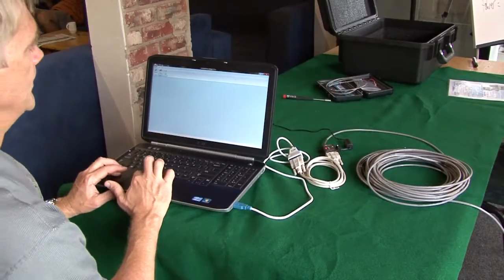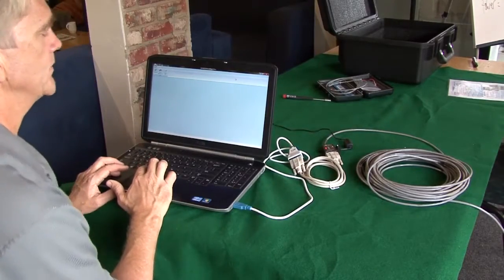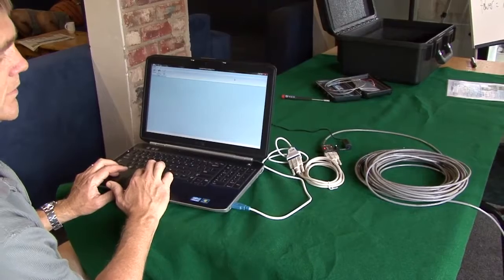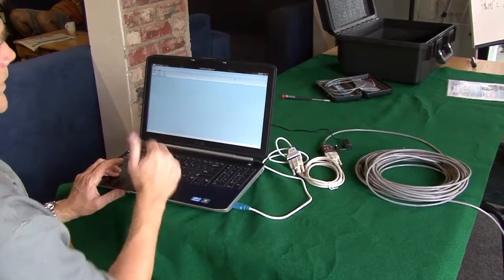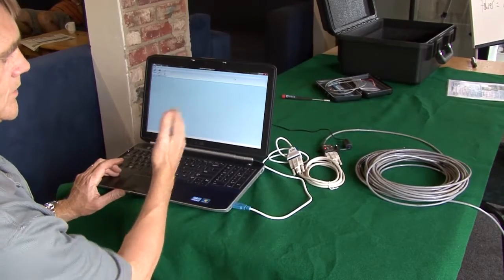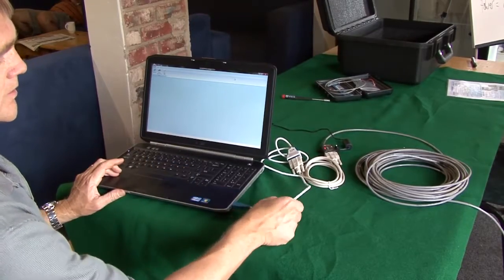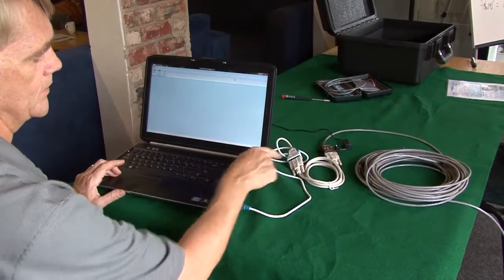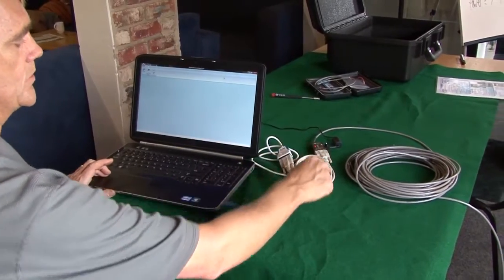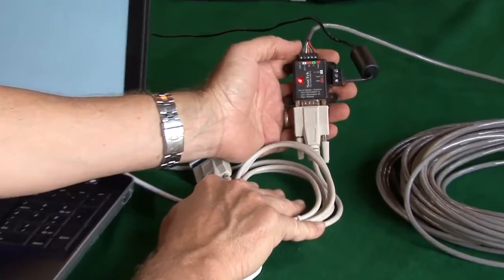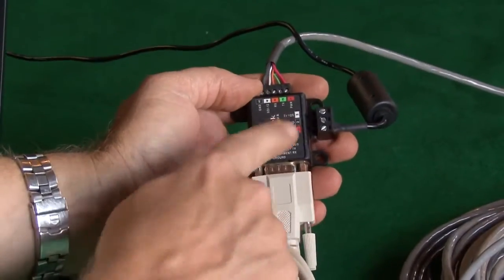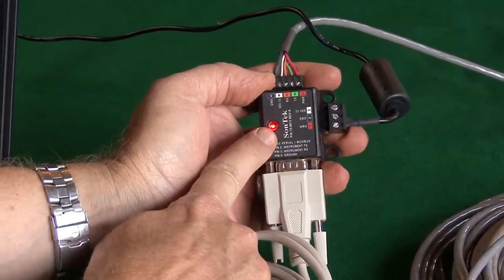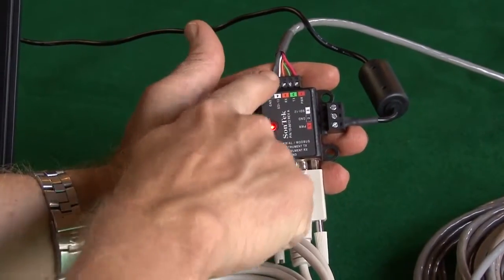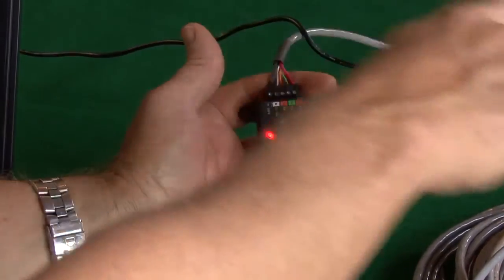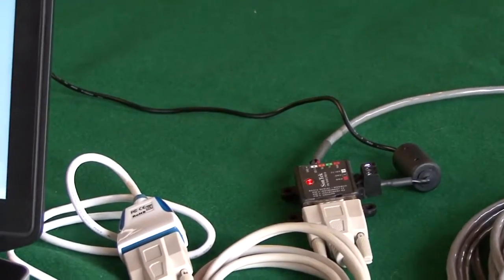What I want to show you here is just a quick example of how to program the instrument once it's been installed. Just briefly, I have the IQ software that I've installed and opened on my laptop. Here's the USB to 232 converter that's plugged into the RS-232 cable. Here's the power and communications interface. Here we're supplying the power. You can see the red light indicates that there's power to the system. And this is the terminal blocks with the cable that goes to the IQ that's installed in the water.